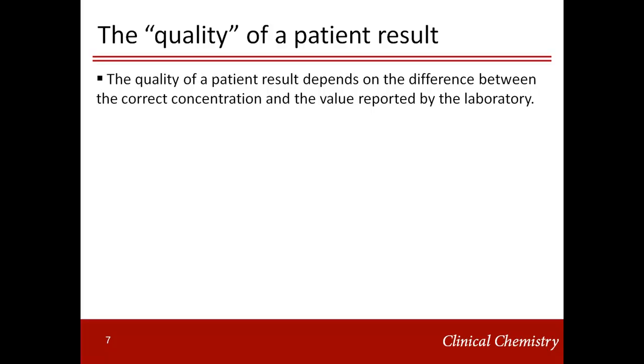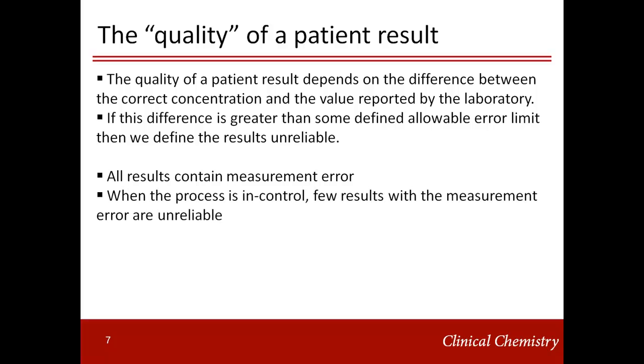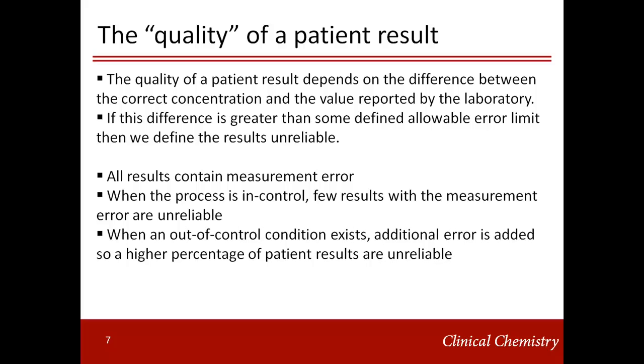Why do we care about these out-of-control conditions? Because we care about the quality of patient results produced. The quality of a patient result depends on the difference between the correct concentration and the value reported by the laboratory. If this difference is greater than a specified allowable error limit, then we define the patient result as unreliable. All patient results contain some measurement error. When the process is in control, only a few results with measurement error are unreliable. When an out-of-control condition exists, additional error is added, so a higher percentage of patient results become unreliable.